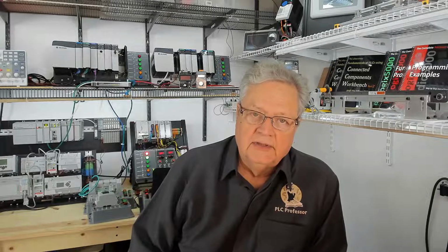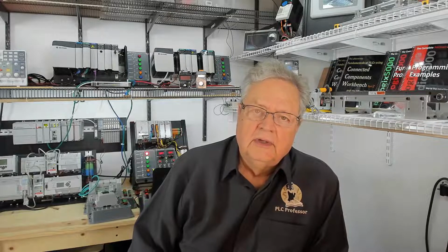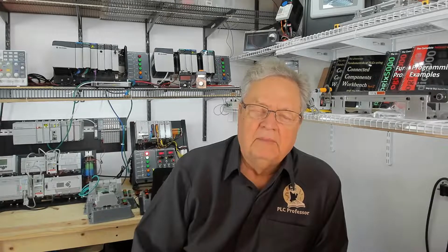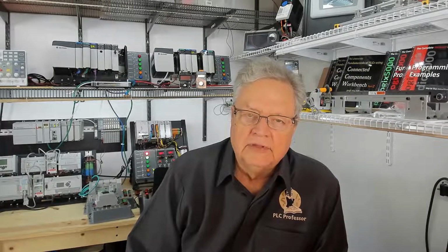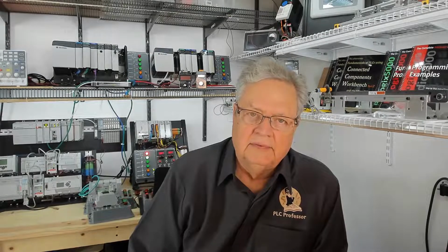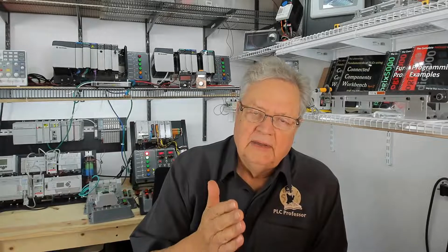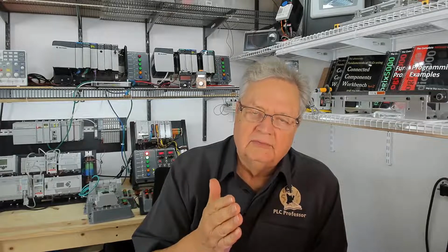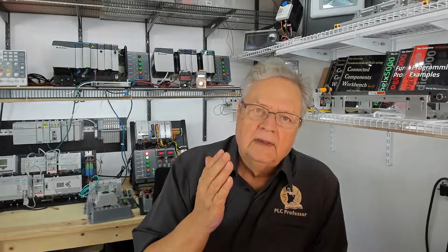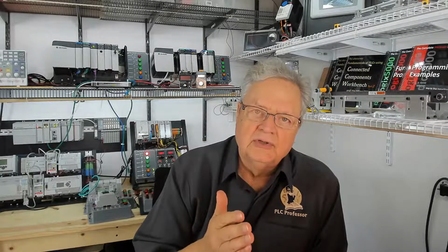ControlLogix, specifically the 1756 I/O, is an order of magnitude more convoluted, more complicated, more capable than the active backplane I/O for SLC500, PLC5, MicroLogix, etc. Each 1756 module of any type that slides into the backplane has a second generation RISC processor, reduced instruction set CPU, and it does communications on its own.